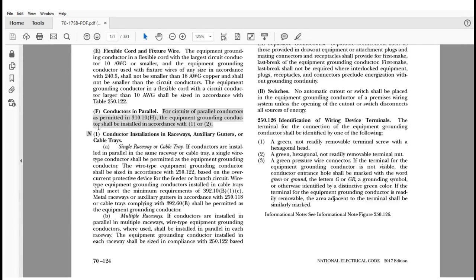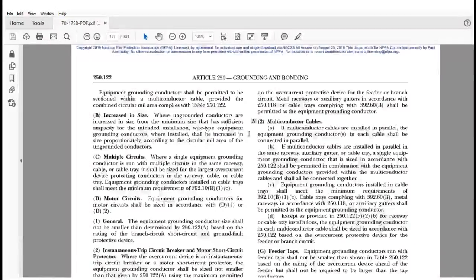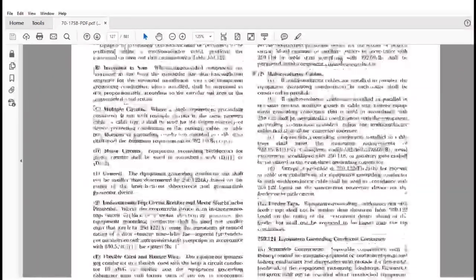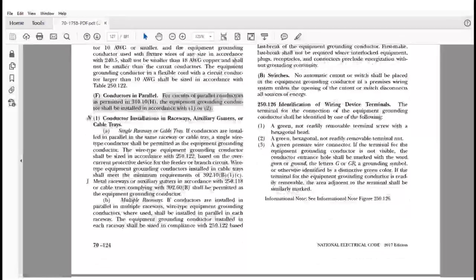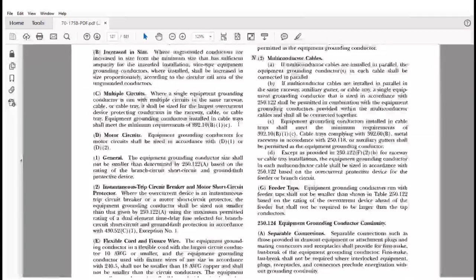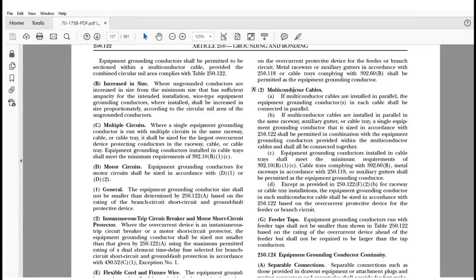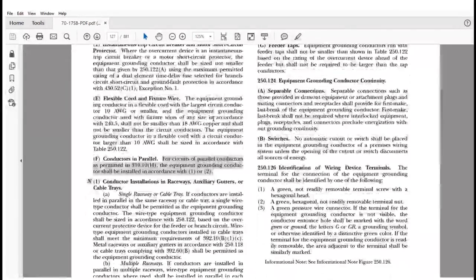Now one thing you will notice is that there are N's here. There's an N on item 1 and an N on item 2, and what it's trying to do is deal with conductors installed in raceways, auxiliary gutters, and cable trays. And now we have direction when you're dealing with multi-conductor cables. These are pretty neat, so we've got to follow through each one of these so that you get a grip on what we're talking about.